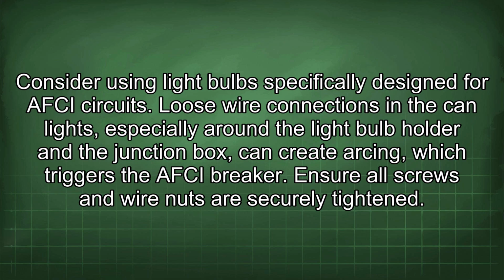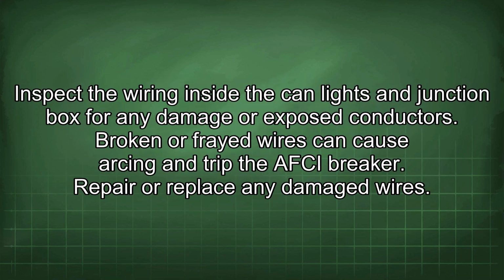Loose wire connections in the can lights, especially around the light bulb holder and the junction box, can create arcing, which triggers the AFCI breaker. Ensure all screws and wire nuts are securely tightened. Inspect the wiring inside the can lights and junction box for any damage or exposed conductors. Broken or frayed wires can cause arcing and trip the AFCI breaker. Repair or replace any damaged wires.